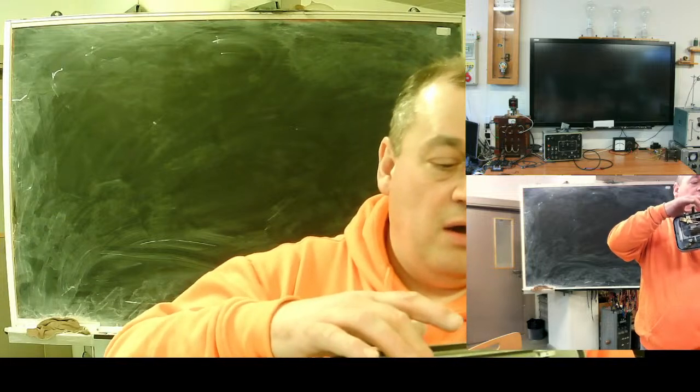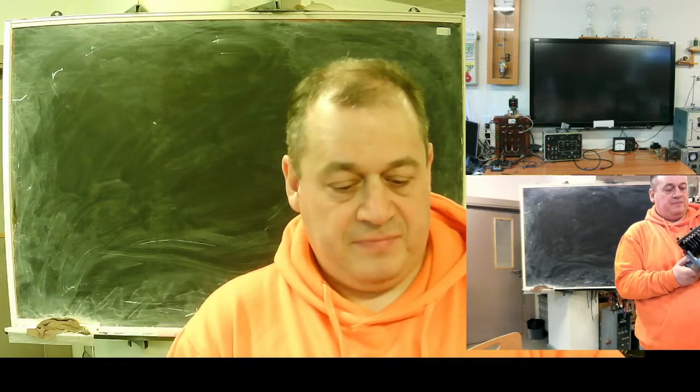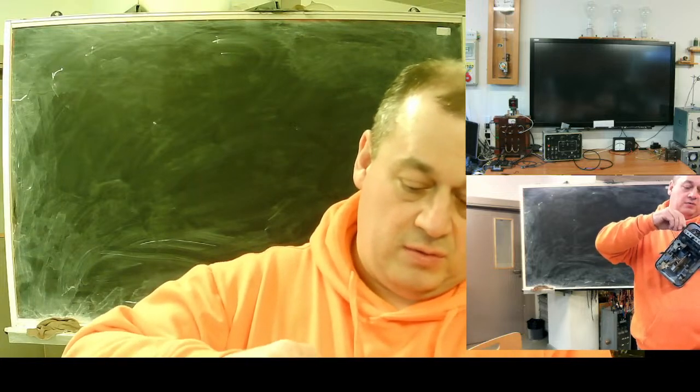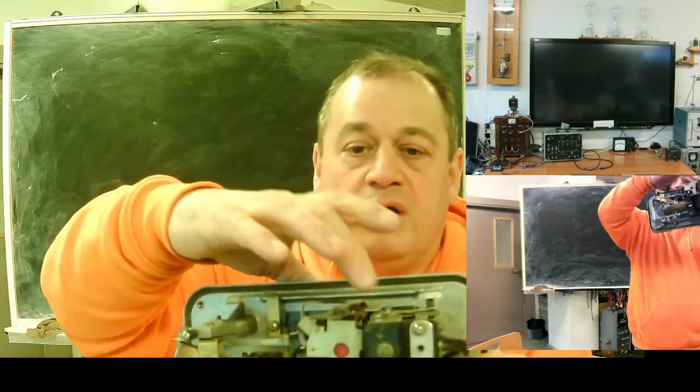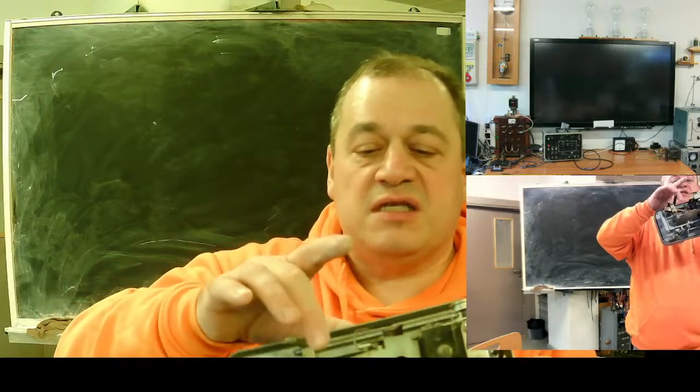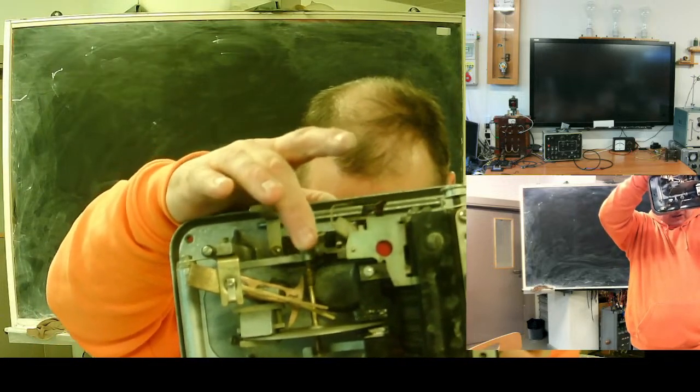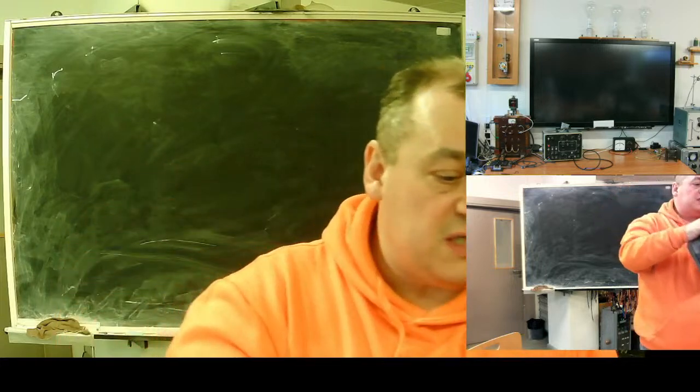When the disk rotates, it shifts the arm up. Arm like this. Shifts up. Yeah, shifts up. I also have this trip indicator. Up, shows a red flag. The arm shifts up and closes this contact.